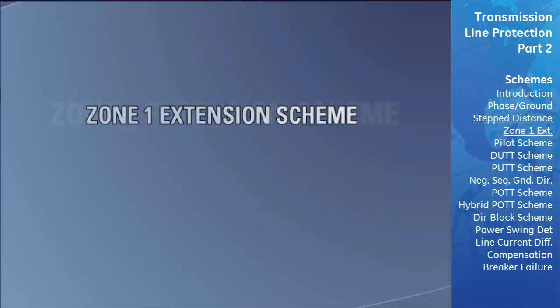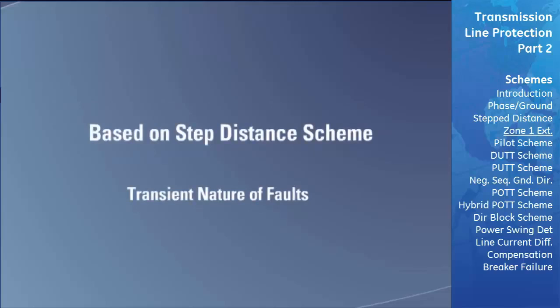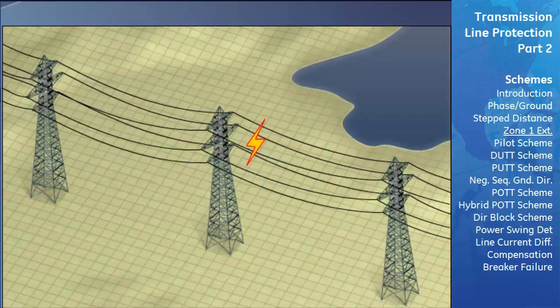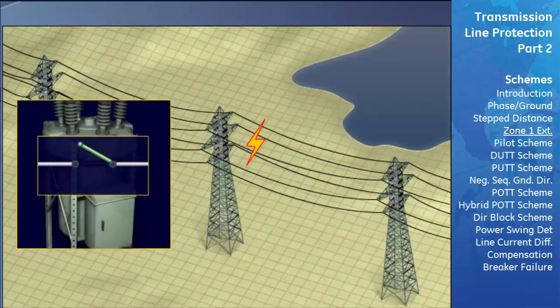The Zone 1 Extension Scheme is an enhancement to the stepped distance scheme. It operates on the principle that most transmission line faults are transient in nature, meaning the fault is not permanent. For example, the most common cause is lightning. If lightning strikes a transmission line, it ionizes the air, reducing resistance between phases and creating a fault. Once the line is tripped and the fault cleared, the ionized air dissipates and the path for current flow is removed. Closing the breaker at this point would re-energize the line and restore power transmission.